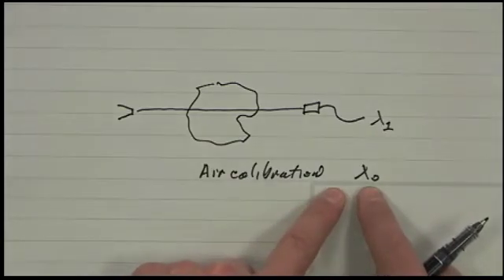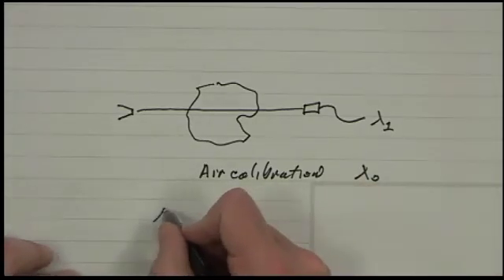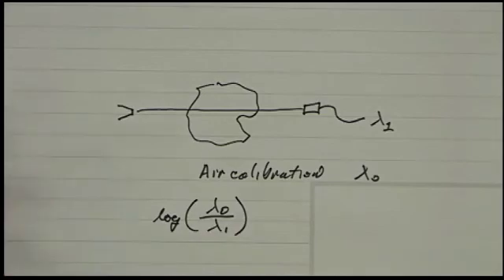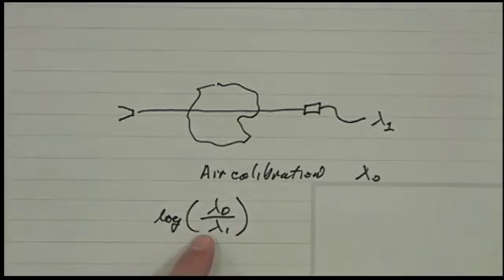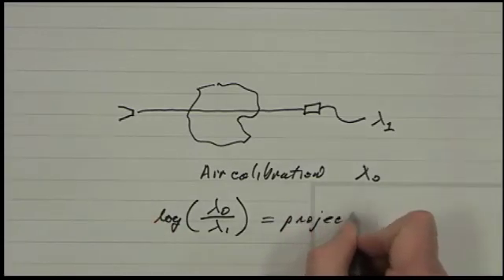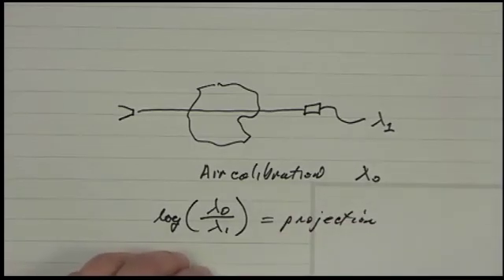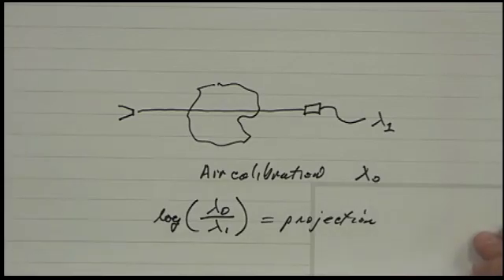And then what you do is you make the measurement lambda when there's something in the system. They do this in the morning before you get there. So in the morning when the technician arrives to work, the first thing they do is they calibrate the system in the morning before they start up, if they're doing the right thing. Then what they do is they take the log of lambda zero over lambda one. This is a positive number. And the log, so that's going to be positive. And that's your projection. So that's the physical measurement that you make. Now, once you have the physical measurement, now we still have the problem that we have to actually invert it.